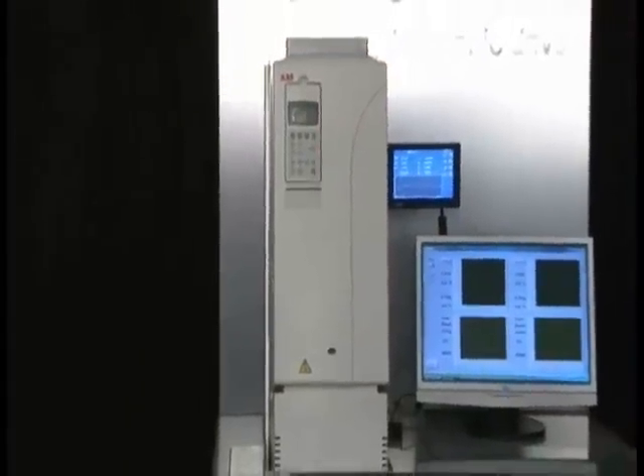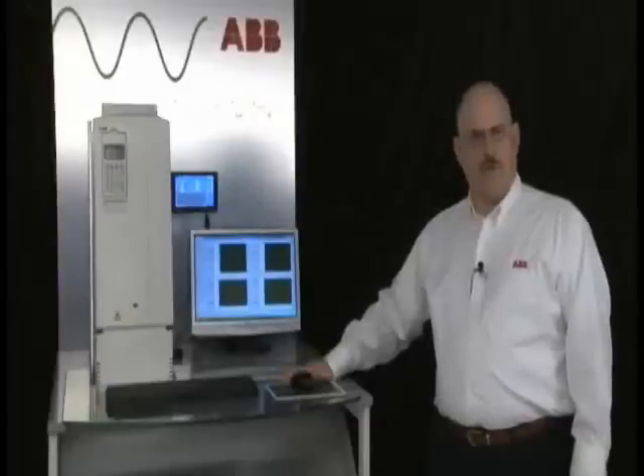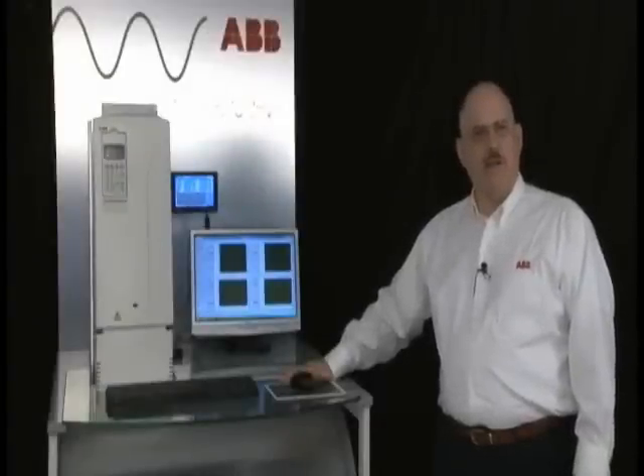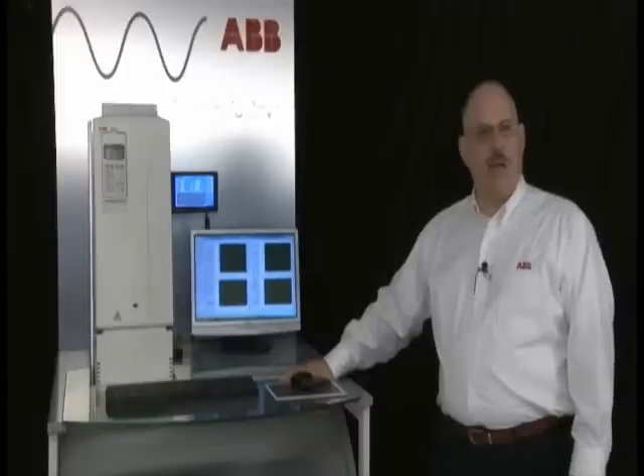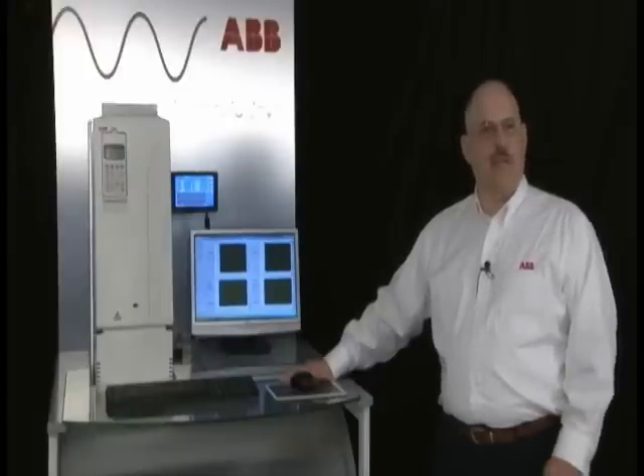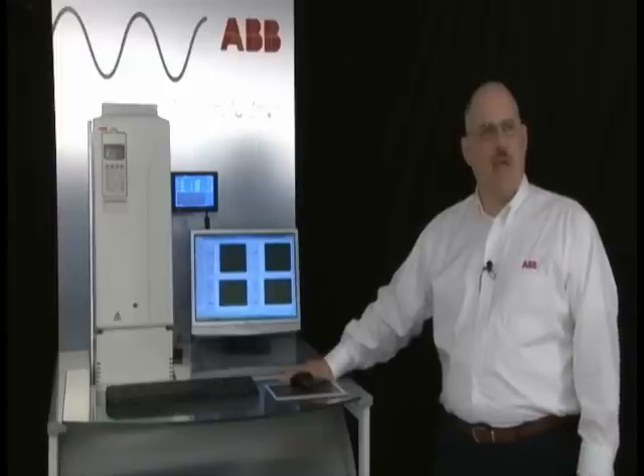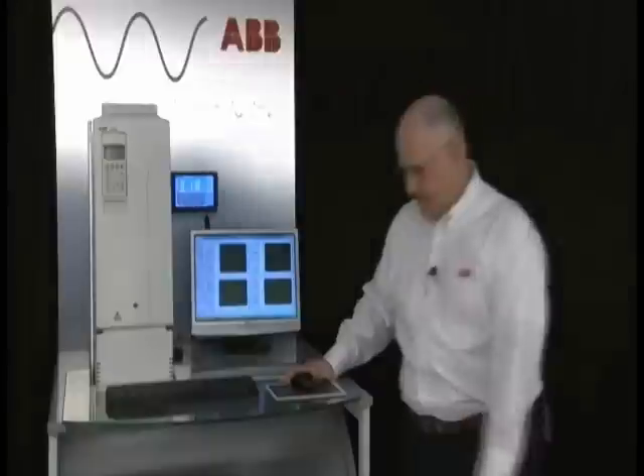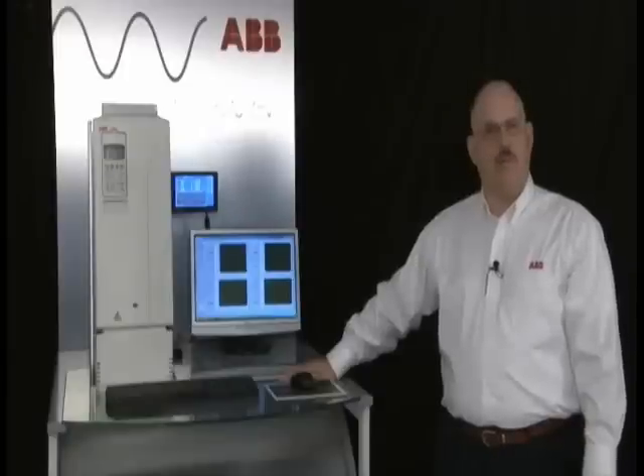We have created an ultra-low harmonic demo unit which allows us to compare and validate different harmonic mitigation technologies on the same distribution system load. This ULH demo system consists of a ULH drive in its entirety and various different front ends that we can attach to this drive: a standard 6-pulse diode front end, that same diode front end with an input line reactor, an 18-pulse transformer with 2 additional 6-pulse bridges, giving us 18 diodes and the transformer, and ultimately, again, the ULH drive. The additional components are all contained in this lower section here, including the 18-pulse transformer and the additional diodes and reactors.